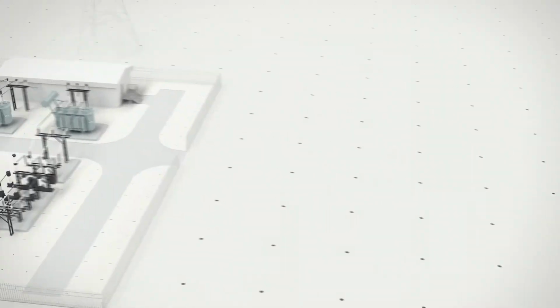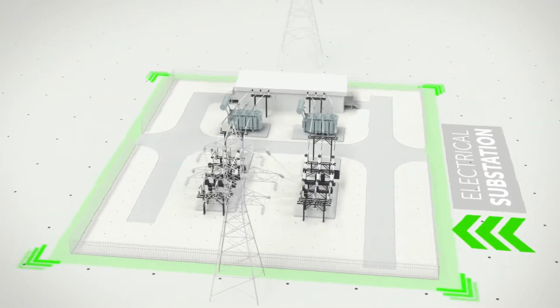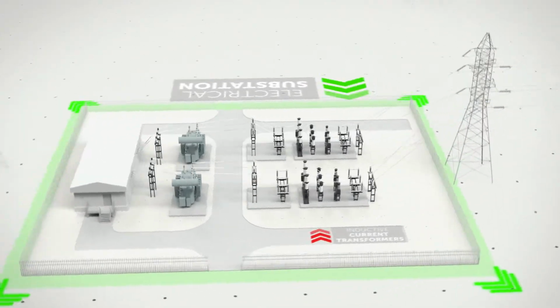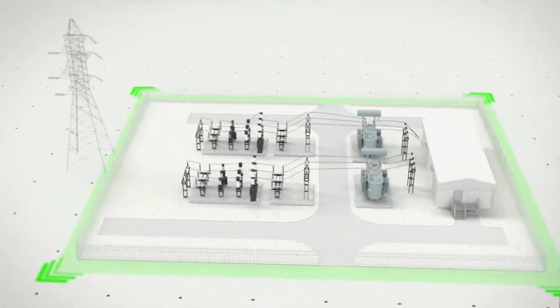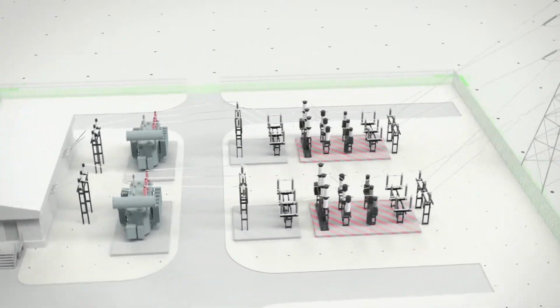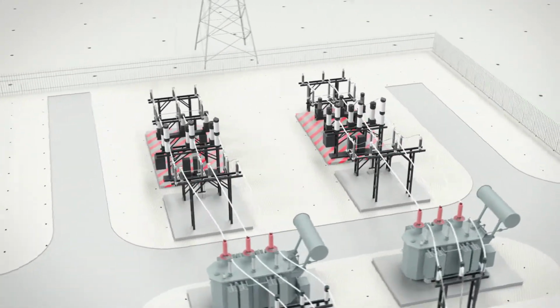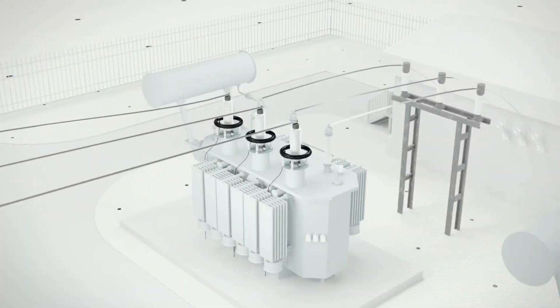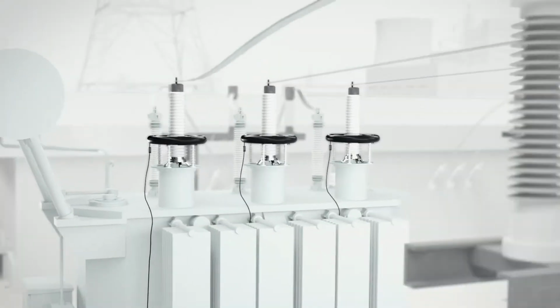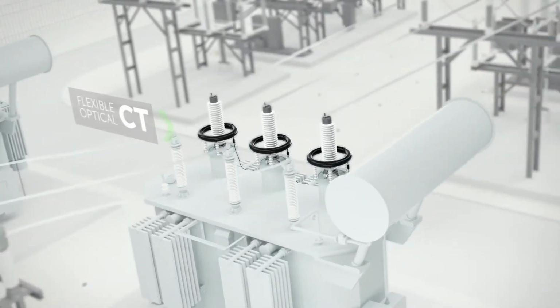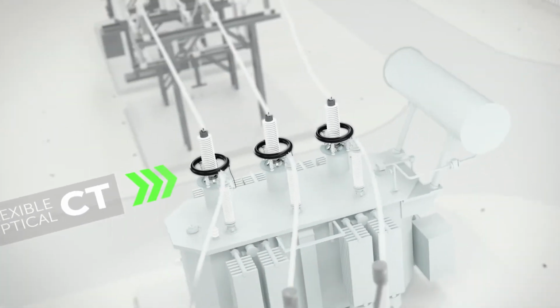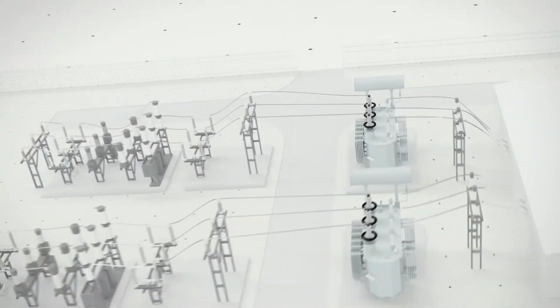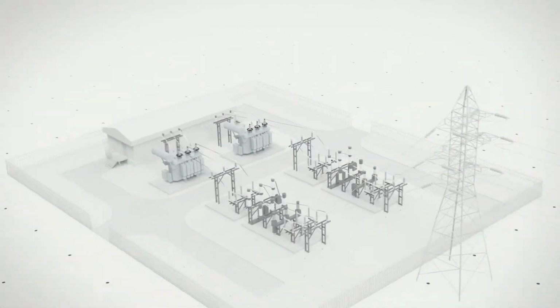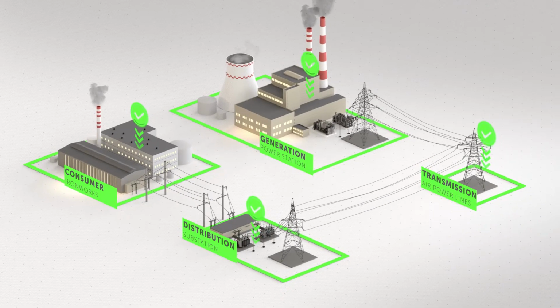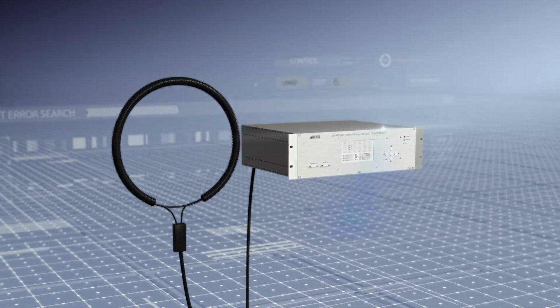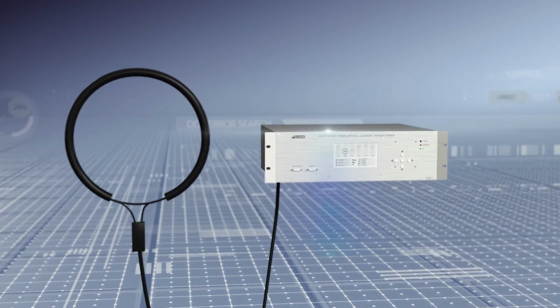Current measurements at a number of points are required for electrical substations to operate reliably. Traditionally, standard inductive CTs were used for this purpose. However, when a point of measurement is required and there is not enough space for a traditional CT, flexible optical CTs come into their own. Optical CTs are capable of making the same measurements as traditional electromagnetic CTs, and with greater accuracy. However, thanks to their compactness and ease of installation, they can be used even at the most congested places in the substation. Our flexible optical current transformer is a compact, accurate and reliable device.